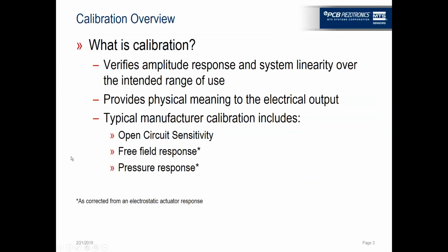So just to do a quick outline here, what is calibration? It is a method of verifying the amplitude response and system linearity over the intended range of use for your microphone. It provides a physical meaning to an electrical output.